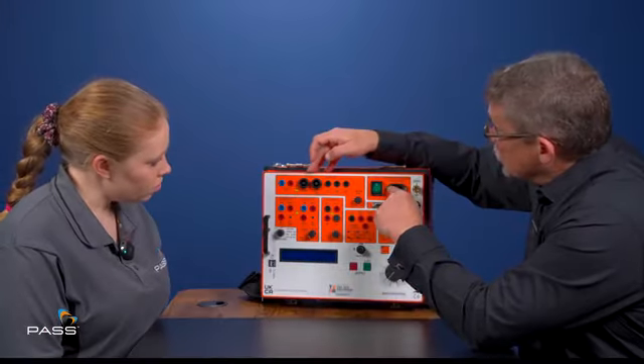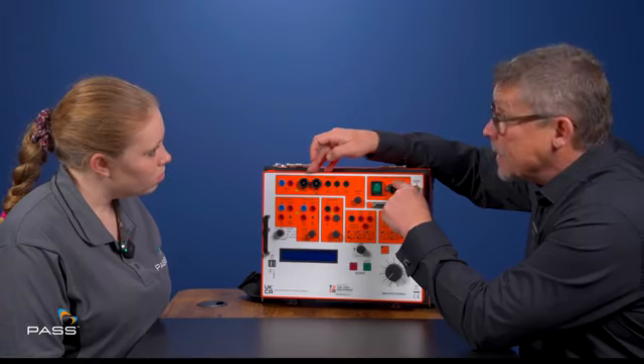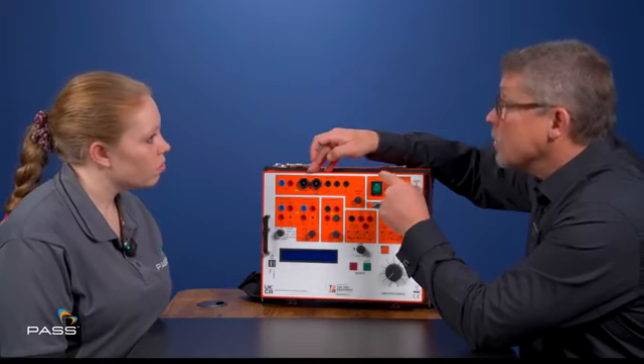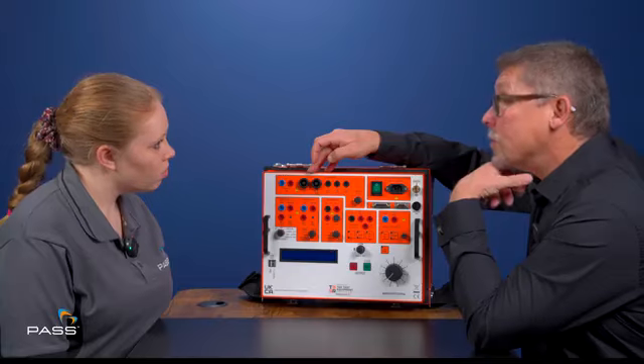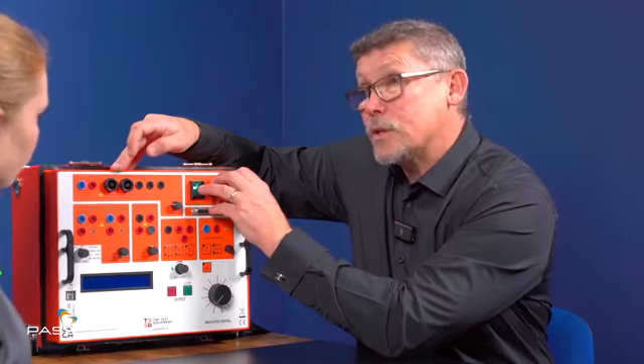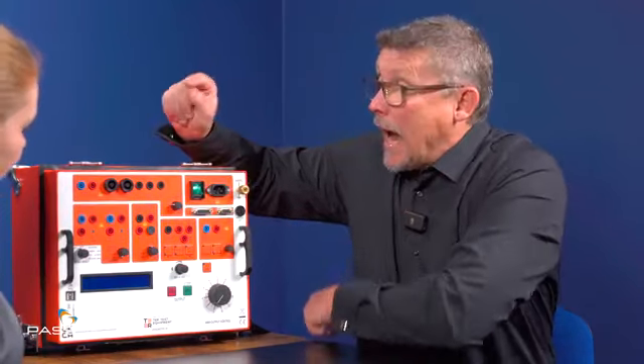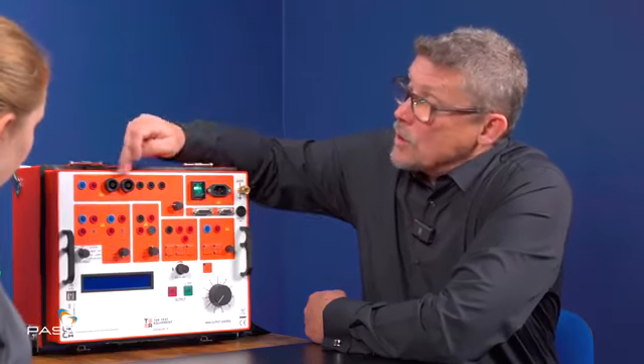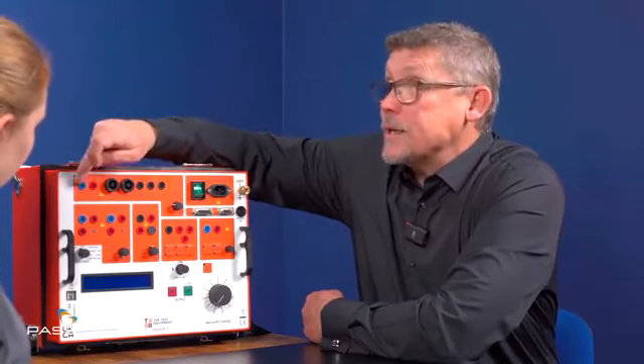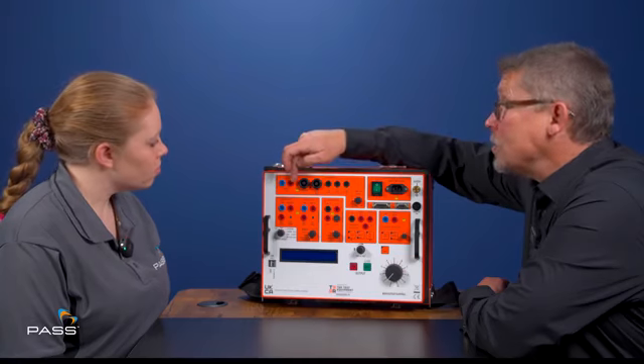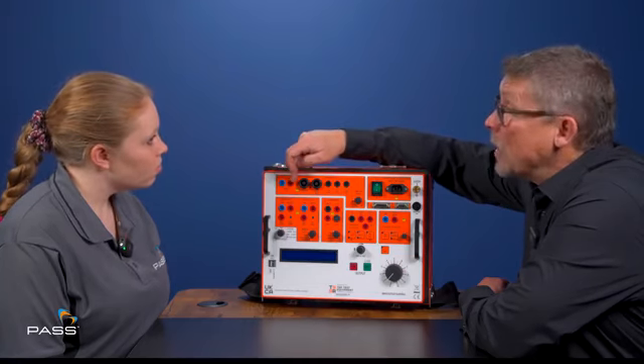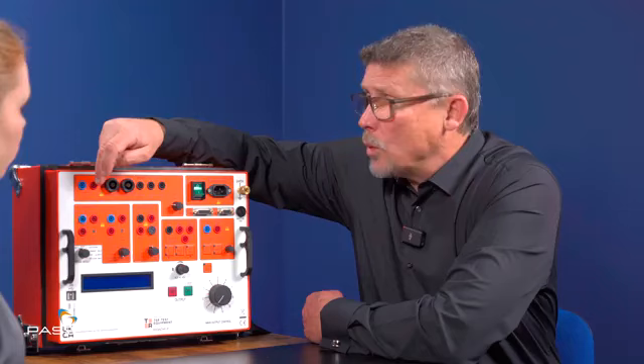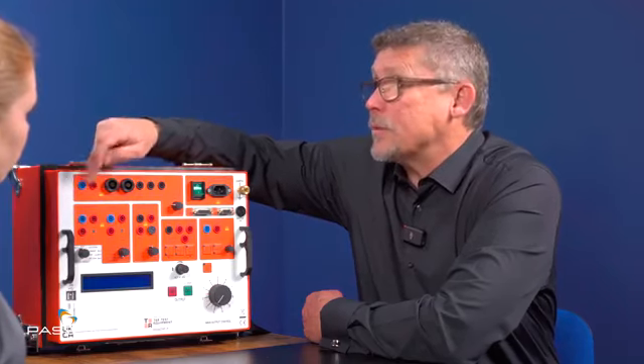And these units are auto-sensing, so they'll give you 50, 60 hertz, 100 or 110, or 240 volts, and it'll auto-select when we connect that. As well as that AC output, we also have this tap here, which is a DC output as well. So we can use this unit on places like the railway, where we'll have smaller, but we still need to test those relays for the DC protection.